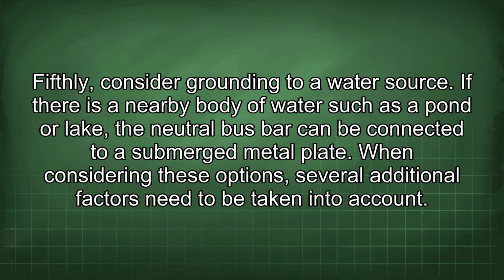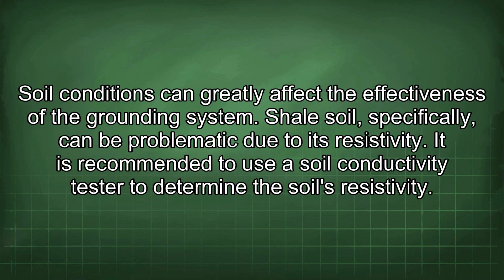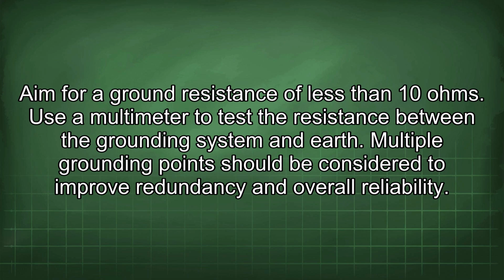When considering these options, several additional factors need to be taken into account. Soil conditions can greatly affect the effectiveness of the grounding system. Shale soil, specifically, can be problematic due to its resistivity. It is recommended to use a soil conductivity tester to determine the soil's resistivity. Aim for a ground resistance of less than 10 ohms. Use a multimeter to test the resistance between the grounding system and earth. Multiple grounding points should be considered to improve redundancy and overall reliability.